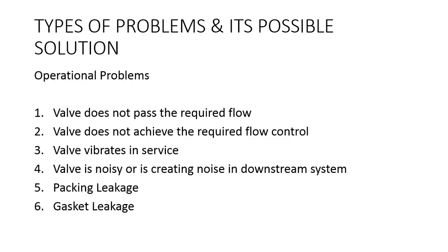Third, valve vibrates in service. It could be due to wear, so check the time period for which the valve is operating. If it is performing well and then begins to vibrate, it means wear has occurred. Line fluid: check for high pressure drop in the line in gas and flashing in liquid. There might be high velocity.